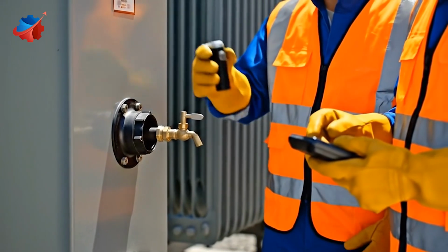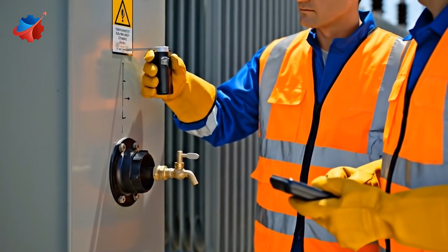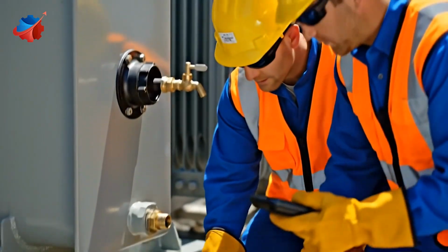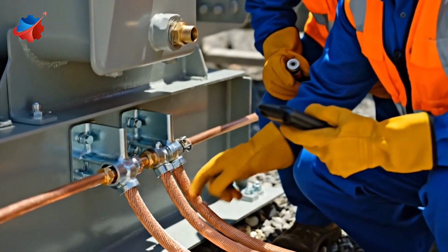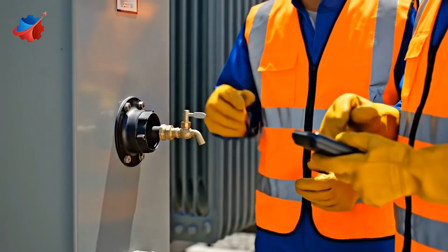Clearance reads 48 inches. That falls within the safe perimeter. Look at this ground connection. It's perfectly tight. Zero corrosion evident. I'll log it.